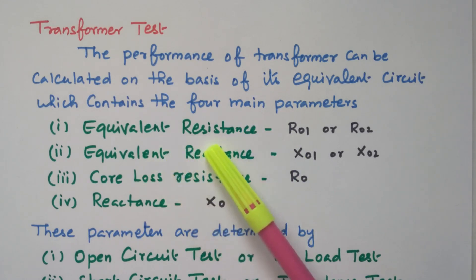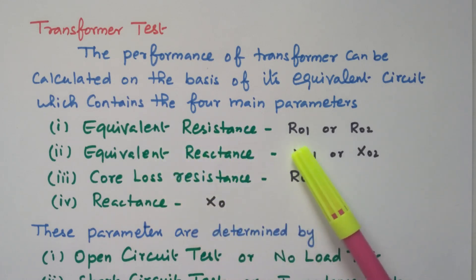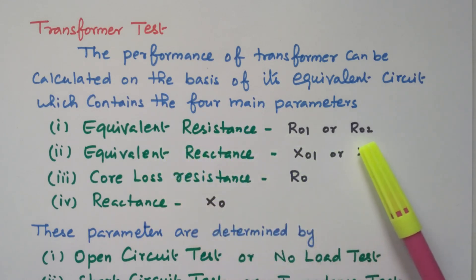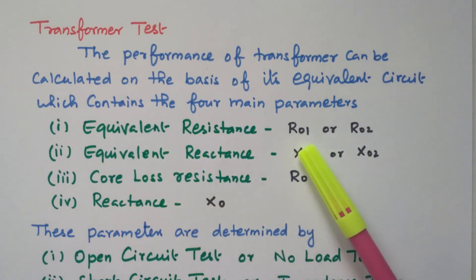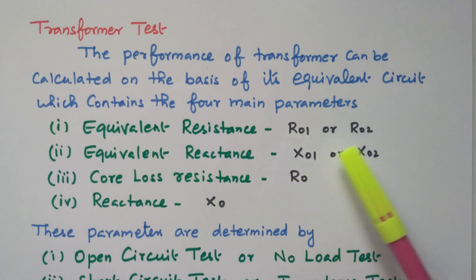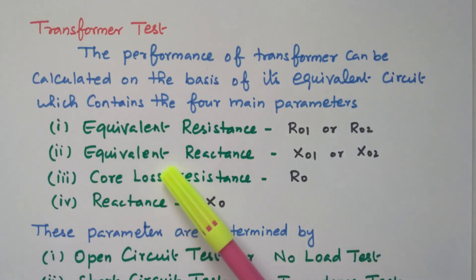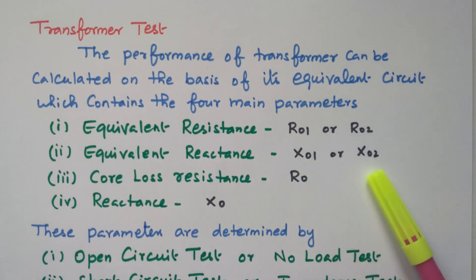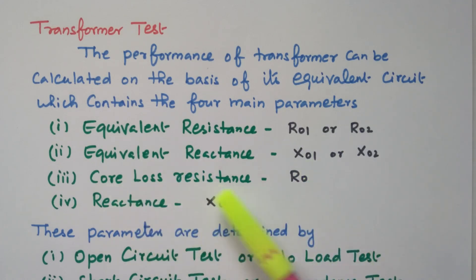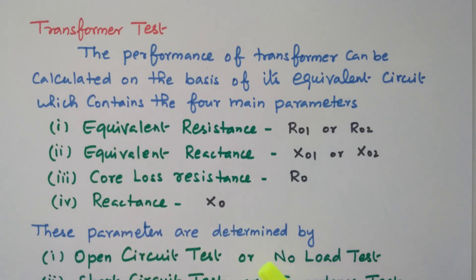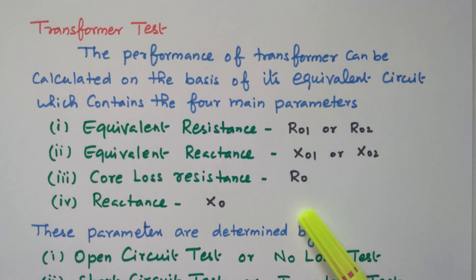The four parameters are: equivalent resistance R01 or R02 — R01 refers to the primary side, R02 to the secondary side — equivalent reactance X01 or X02, core loss resistance R0, and reactance X0. Using these four parameters, we can construct the equivalent circuit.